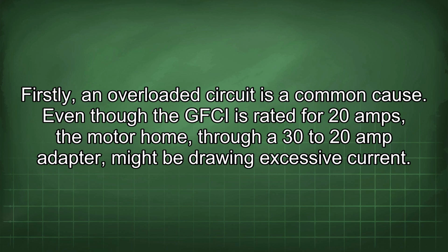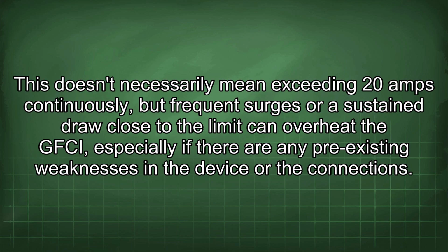Even though the GFCI is rated for 20 amps, the motorhome, through a 30 to 20 amp adapter, might be drawing excessive current. This doesn't necessarily mean exceeding 20 amps continuously, but frequent surges or a sustained draw close to the limit can overheat the GFCI, especially if there are any pre-existing weaknesses in the device or the connections.